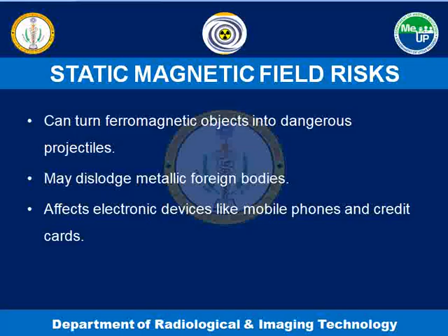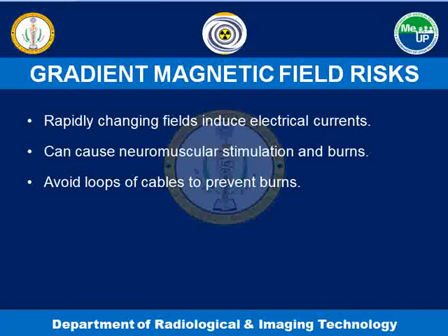Next, static magnetic field risks. It can turn ferromagnetic objects into dangerous projectiles, may dislodge metallic foreign bodies, and affects electronic devices like mobile phones and credit cards. Next, gradient magnetic field risks. Rapidly changing fields induce electrical currents and can cause neuromuscular stimulation and burns. Avoid loops of cables to prevent burns.